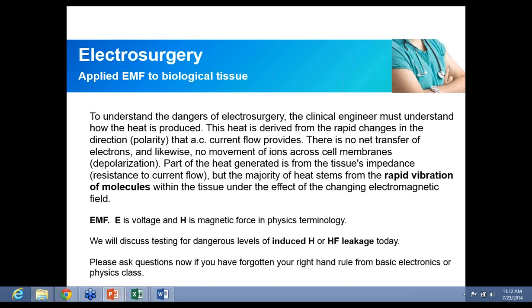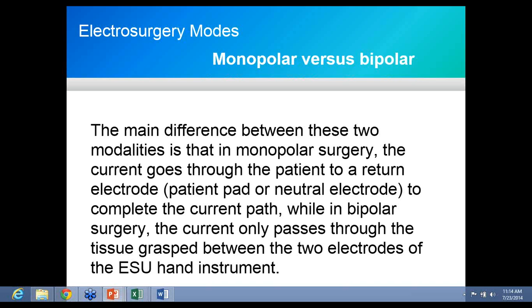So if you have any further questions on that, we'll give you some email references at the end of the webinar. Now on to what's the difference between monopolar and bipolar. I'm sure most of you know this, but in monopolar, the current flows from the active electrode that the surgeon is in control of to a patient pad, sometimes called a neutral electrode, or a dispersive electrode. That's what monopolar is. Bipolar is when that current passes between a set of tweezers or some other type of small bipolar instrument. Bipolar is inherently more safe because the current path is much shorter.